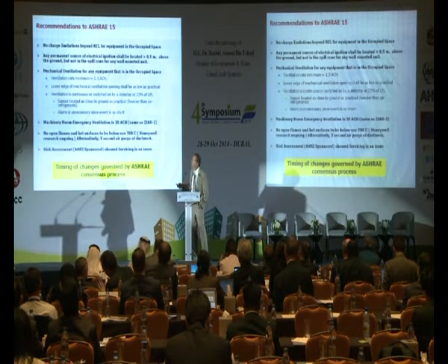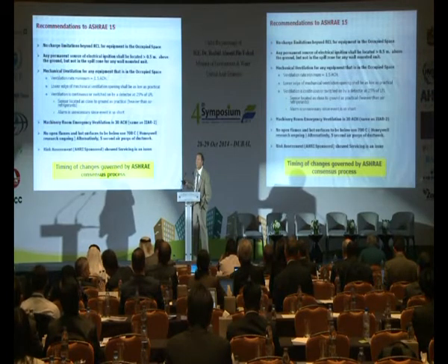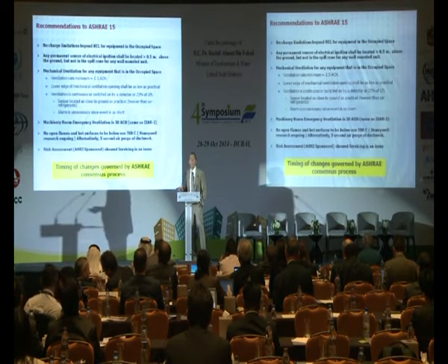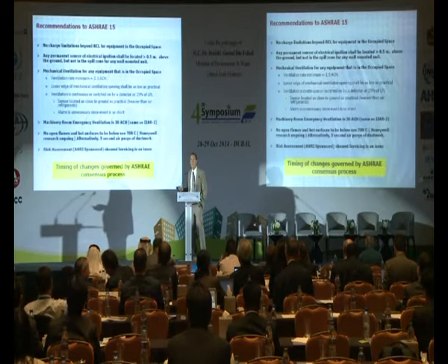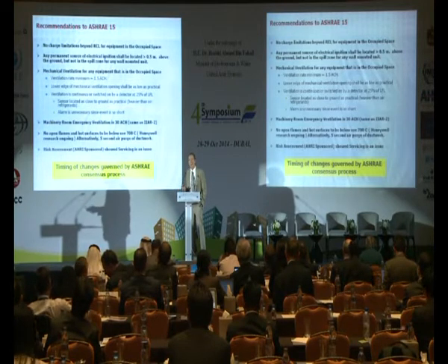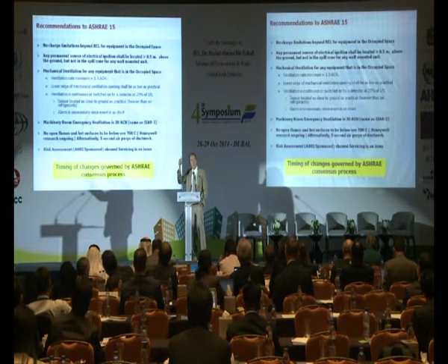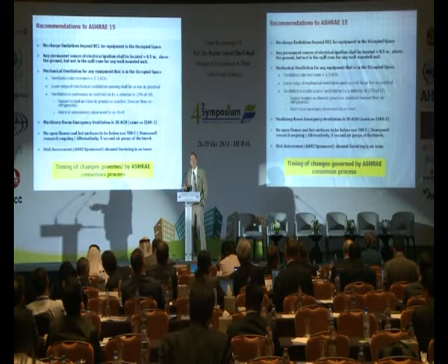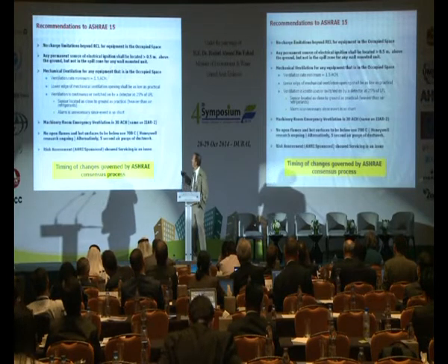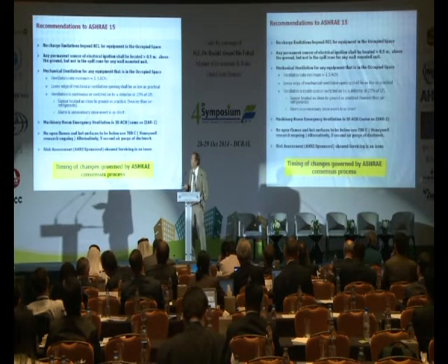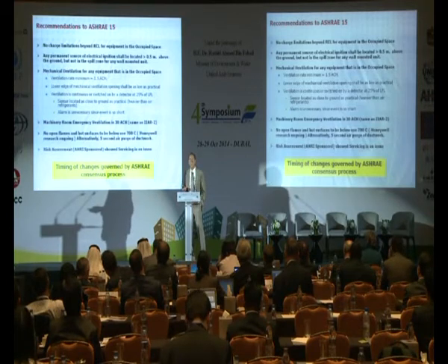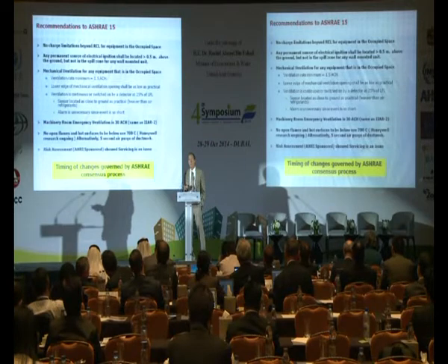I don't think this is unique, but a little different approach. Honeywell has been doing a lot of work to try and understand how hot a surface will really ignite these refrigerants in a ducted situation where we have heaters, that type of thing. We don't want any open flames, that's for sure, but in a ducted situation, we don't want any hot surfaces that are above 700 C, and that's a value that could change.